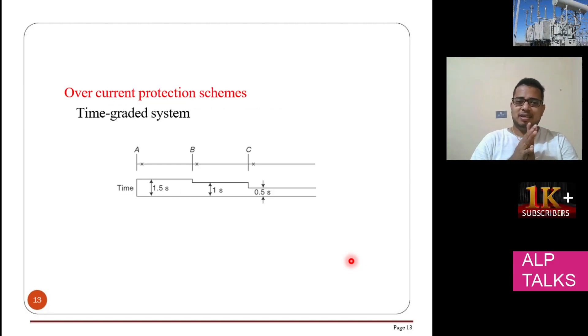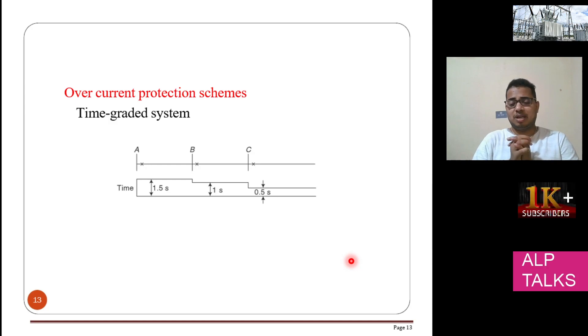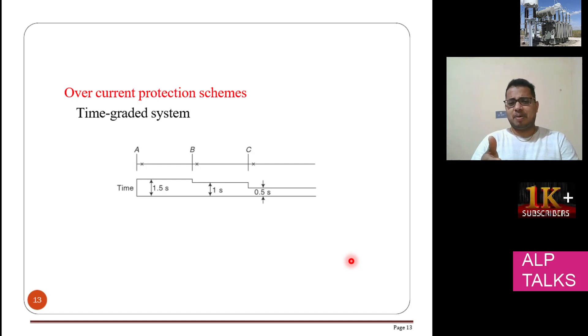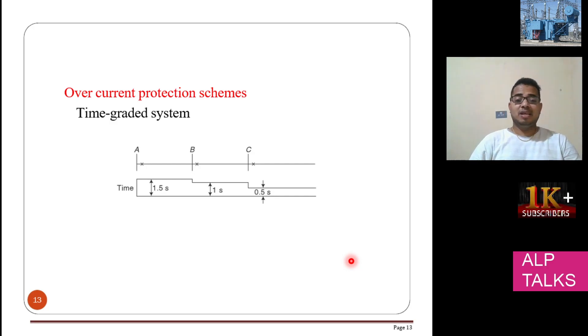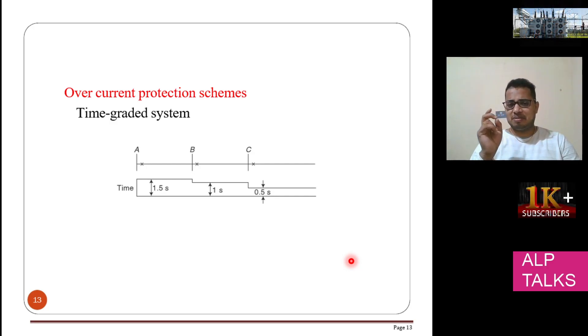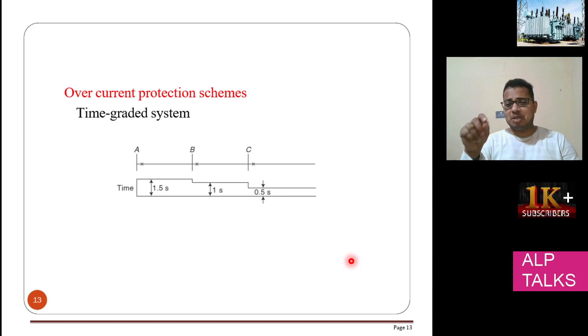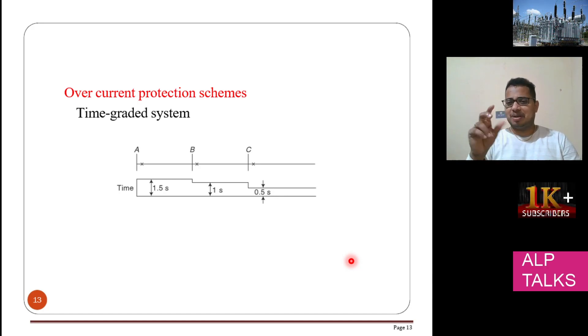There are certain protection schemes. For example, you have a long line with relays at points A, B, and C — A at the start, C at the end, and B in the middle. If a fault happens at the end of the line, C operates at 0.5 seconds, then B at 1 second, then A at 1.5 seconds. This is a time-graded system, which provides a type of backup protection. If C does not operate, after 1 second B will operate. If both B and C fail, after 1.5 seconds A will operate.